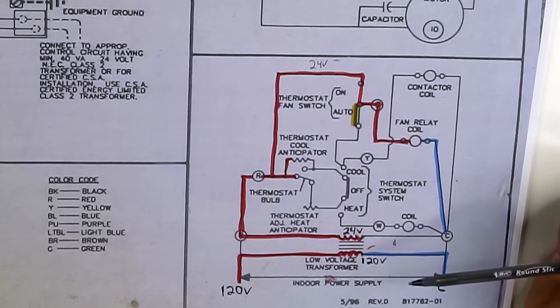The junction box is right there. On the bottom it says controls shown with thermostat in the off position. All these wiring diagrams show what they would look like with the thermostat off or not calling for cooling. If the thermostat was calling for cooling and the system was running, the contactor contacts would be closed and the potential relay switch would be open. Pretty much all wiring diagrams show the unit in the off position. At the bottom we have three notes — note one is about the low voltage, note two is by the hard start capacitor (SA = start assist), and note three is about the equipment ground.